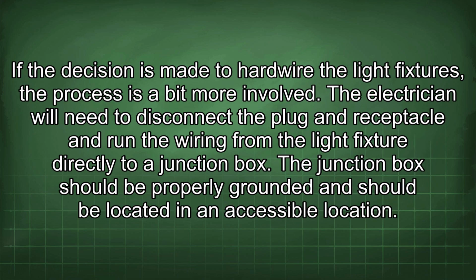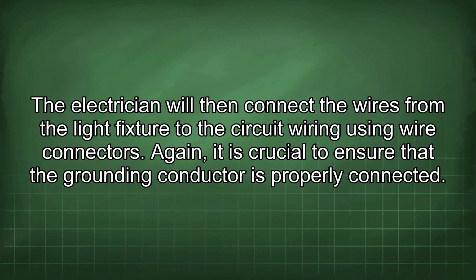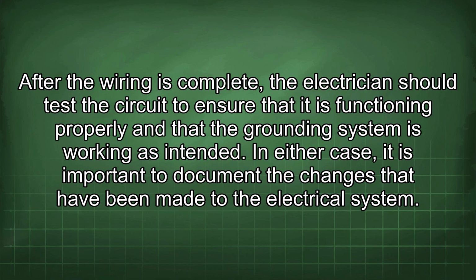The electrician should also test the connection to ensure that it is secure and that the grounding system is functioning properly. If the decision is made to hardwire the light fixtures, the process is a bit more involved. The electrician will need to disconnect the plug and receptacle and run the wiring from the light fixture directly to a junction box. The junction box should be properly grounded and should be located in an accessible location. The electrician will then connect the wires from the light fixture to the circuit wiring using wire connectors. Again, it is crucial to ensure that the grounding conductor is properly connected. After the wiring is complete, the electrician should test the circuit to ensure that it is functioning properly and that the grounding system is working as intended.